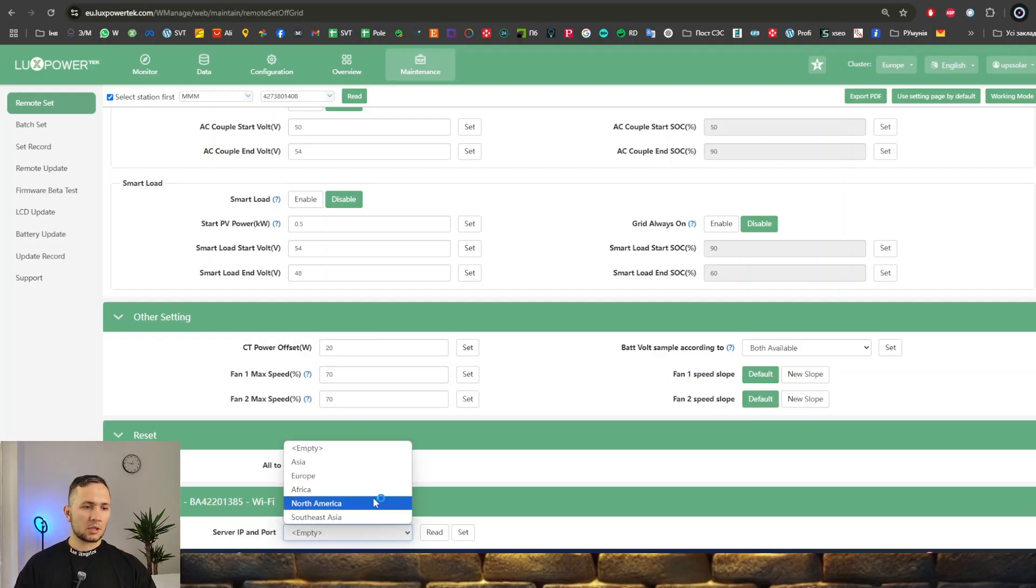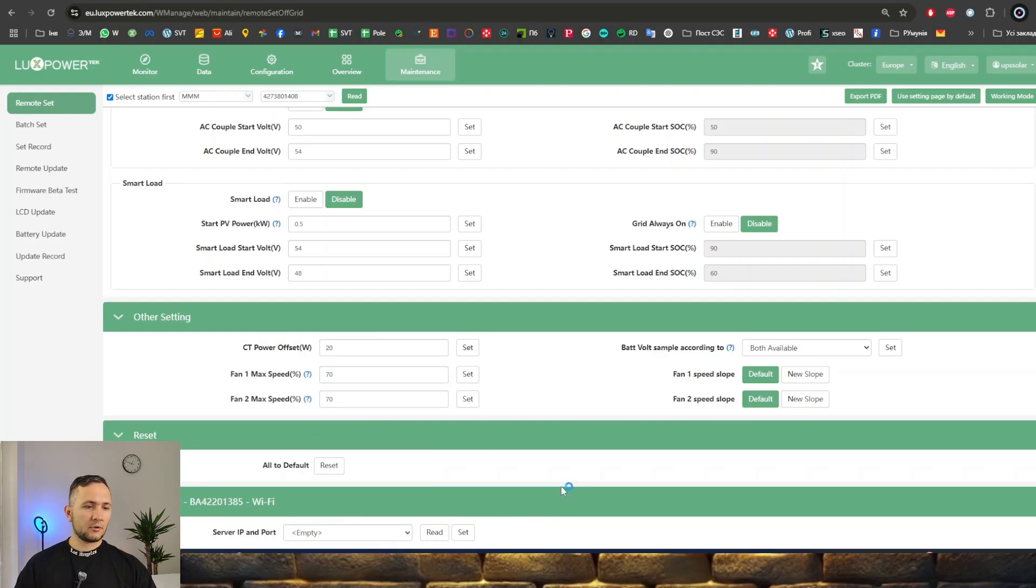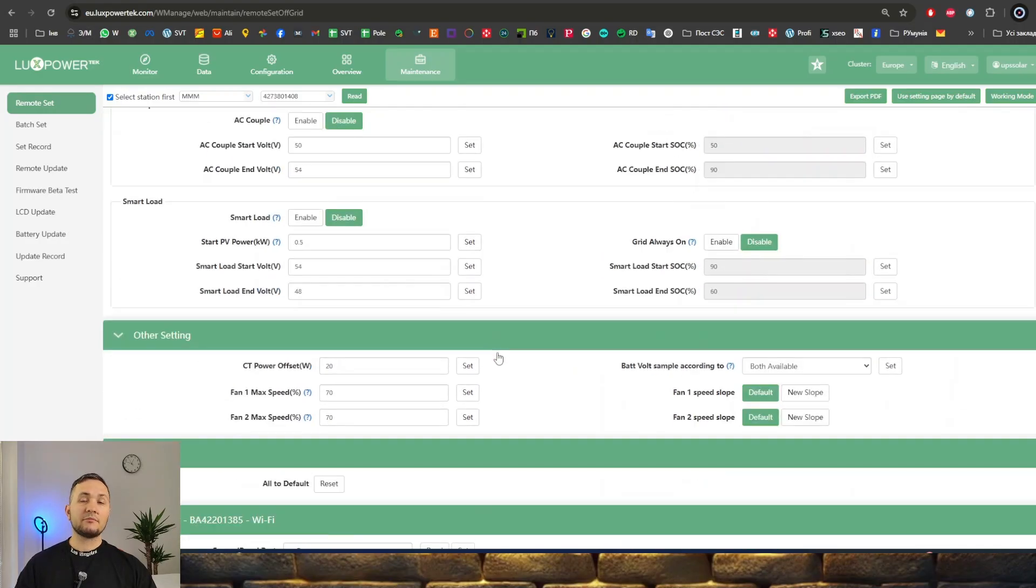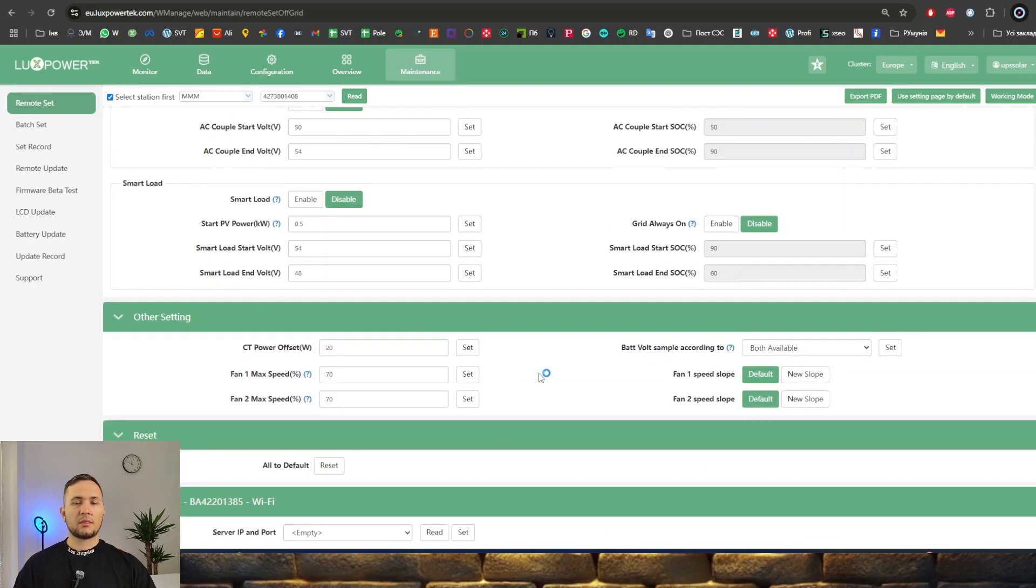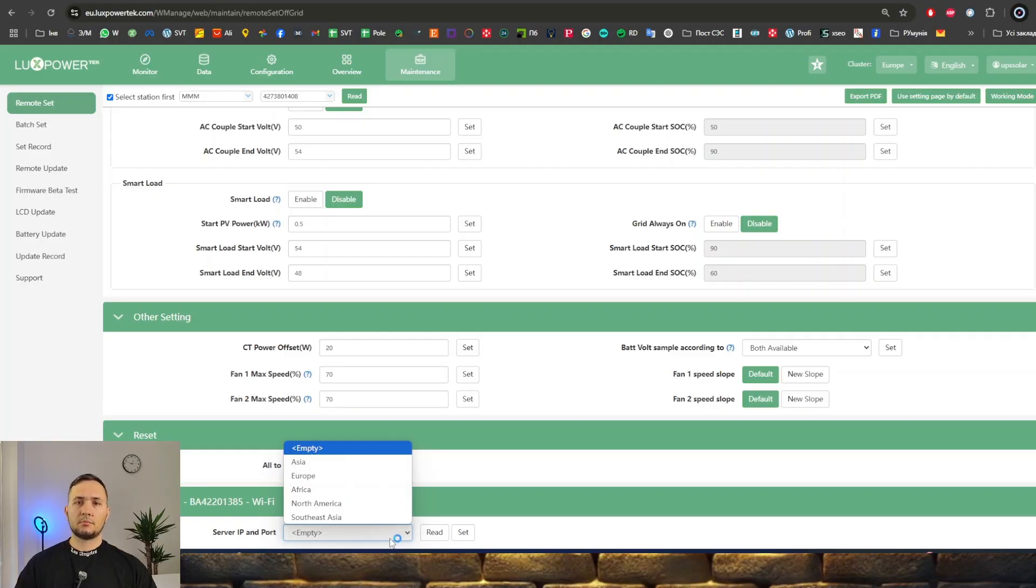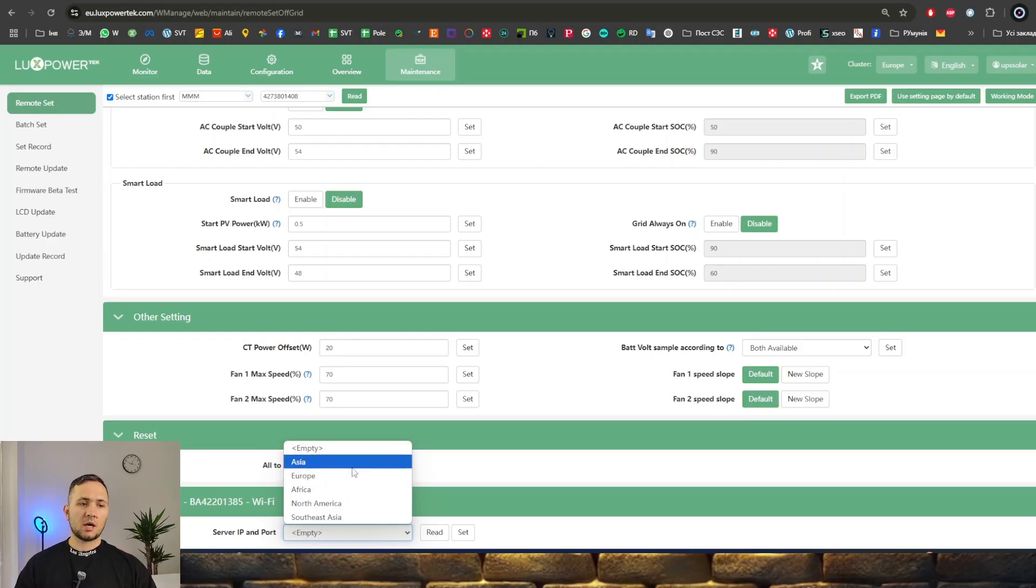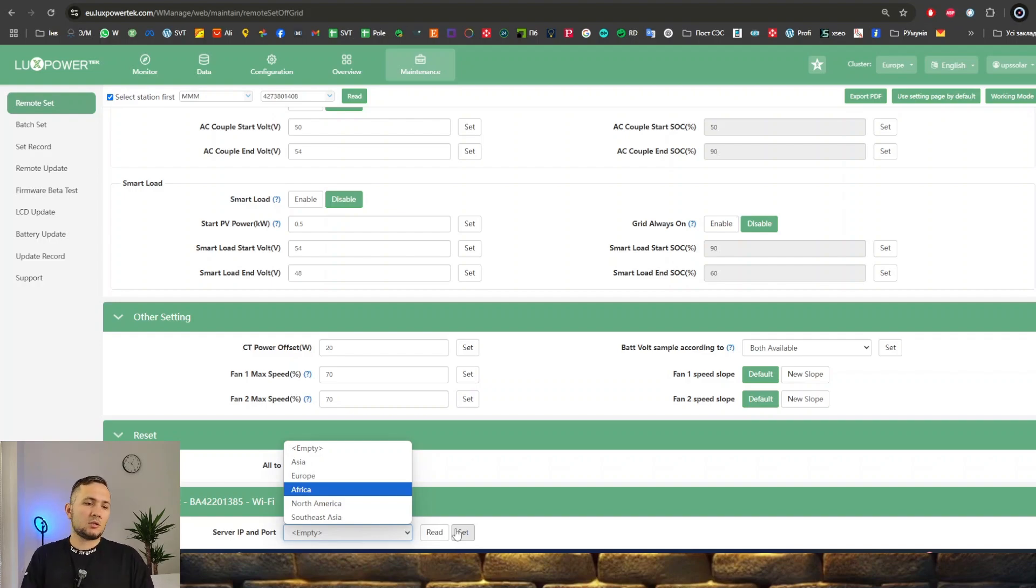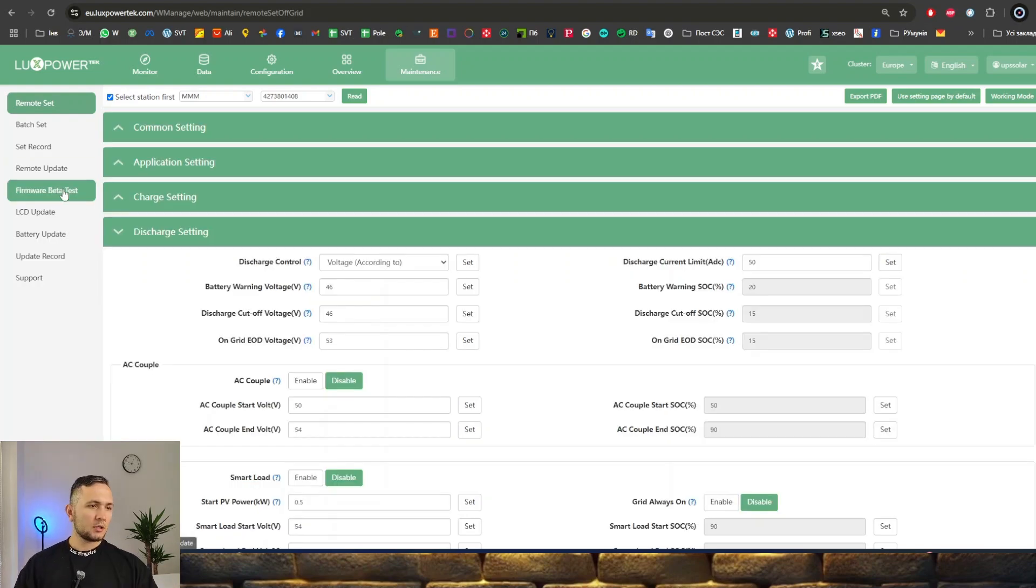Here you can also set the cluster of your inverter. It's important if you have a few inverters and want to get them in a parallel system. If the inverters you bought first and second were in different years, mostly inverters made before 2023 are connected to Asia cluster. If you buy a new one and try to make a parallel system from new and old ones, you need to change clusters to the same.